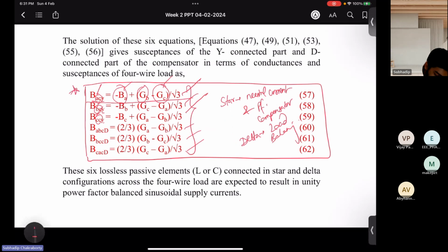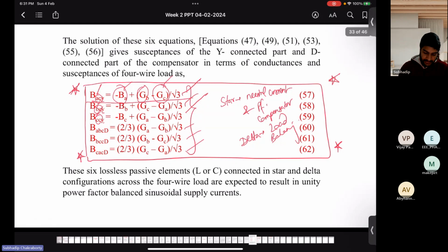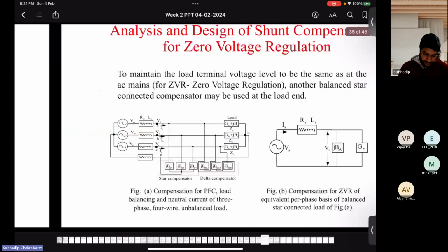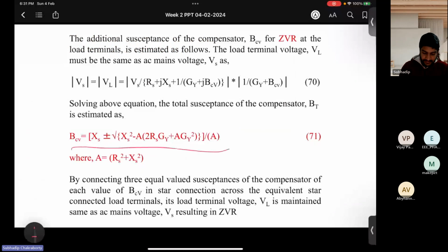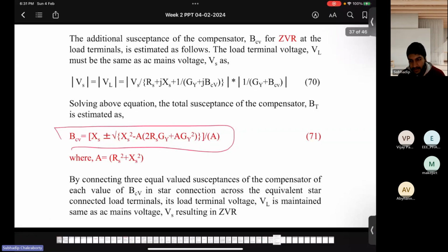So you remember this formula, and with this most of the problems will get solved. If you are clear with the concepts, then you can solve most of the problems. So the ZVR formula remains the same per phase, right? You break it down into per phase, put in the values of the load conductance, and get the value of the compensator for that phase needed for zero voltage regulation. So on a per phase basis, you can calculate all the compensator values for zero voltage regulation.